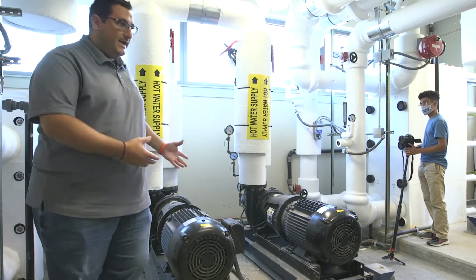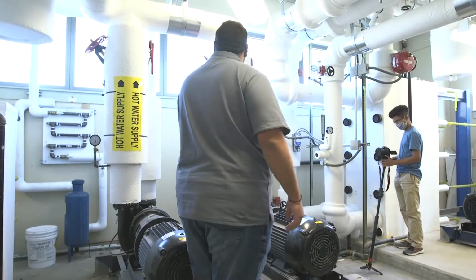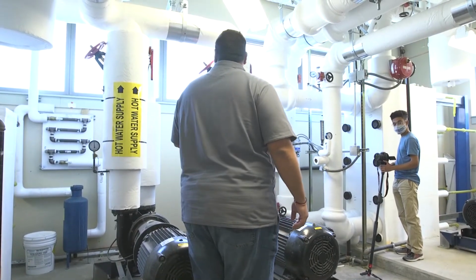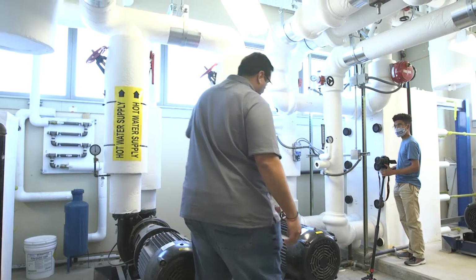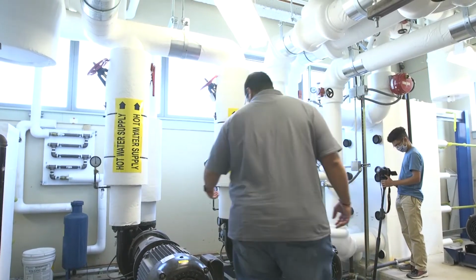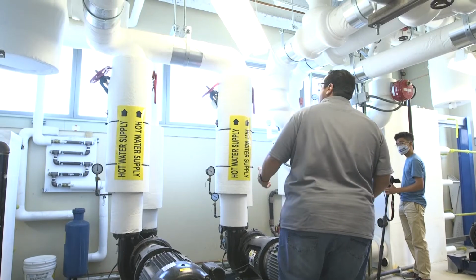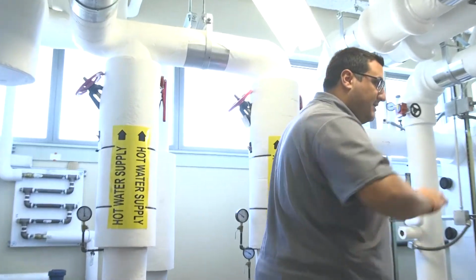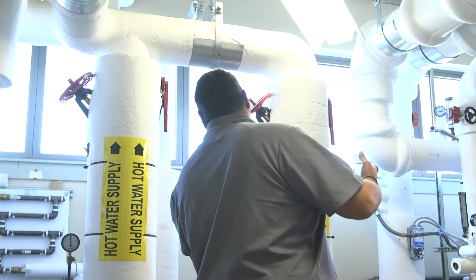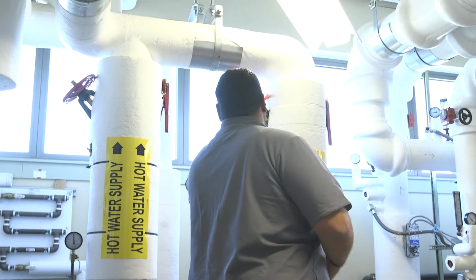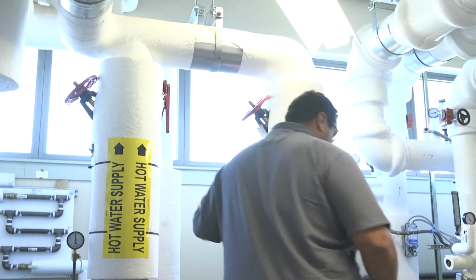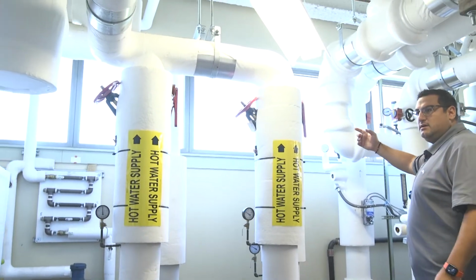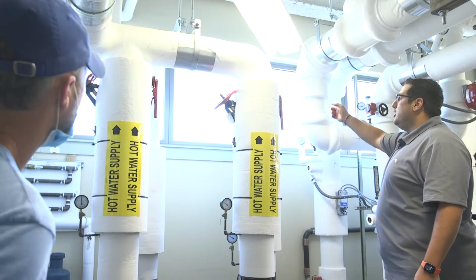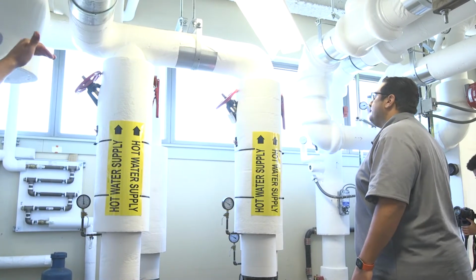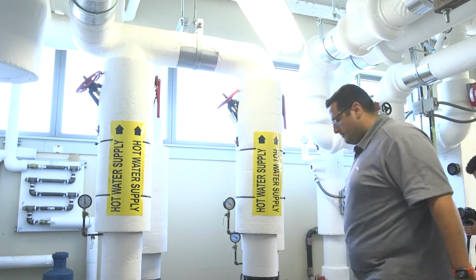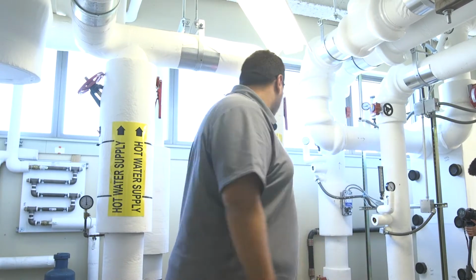That's basically the end suction pump. Those valves over there, one is the isolation valve, that butterfly. On another side. Yeah, one's here, okay. This is isolation. I'm not sure how they have that set up. I'm here for the pumps. This looks like a triple. Oh, it's a check. Okay. That's a triple duty valve. It is a triple duty. Why did they put this butterfly on the other side? Because they have isolation on the inlet. Oh, okay, I see. Yeah, they wanted isolation and the triple duty valve separate. That's okay. That's fine. So you close them both and you're good.